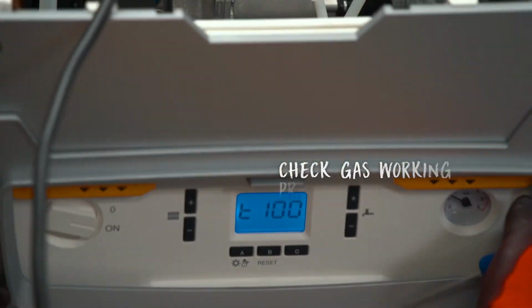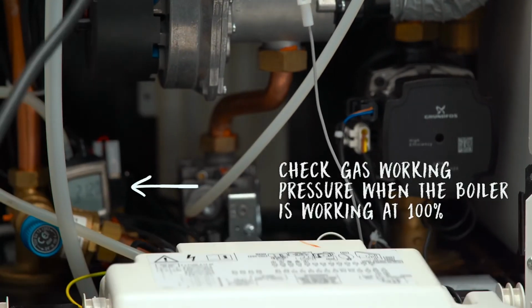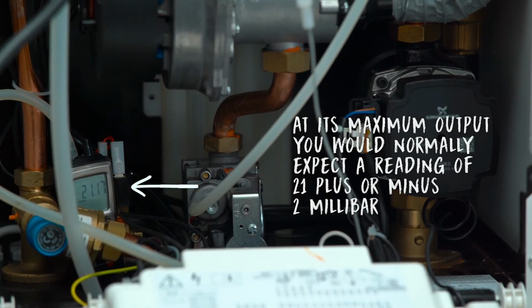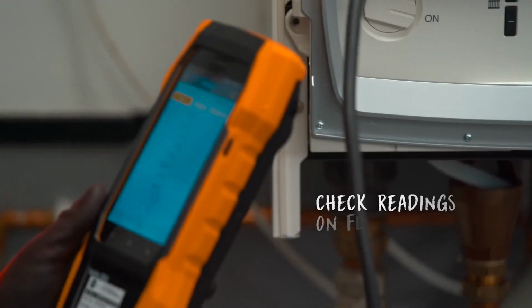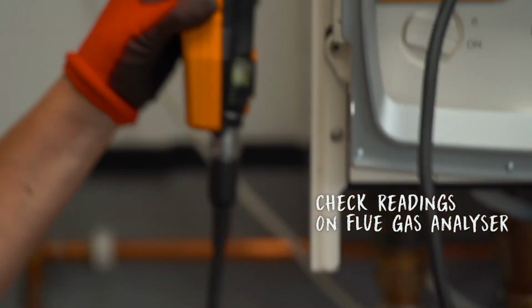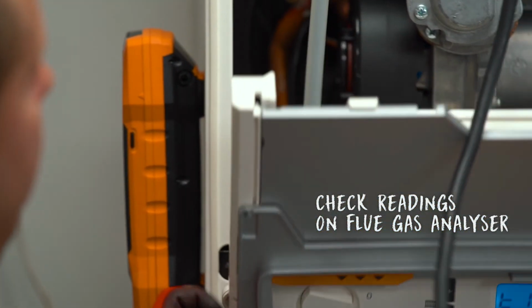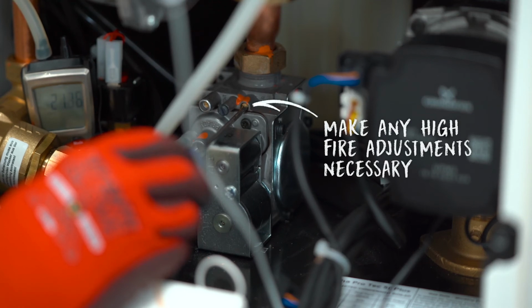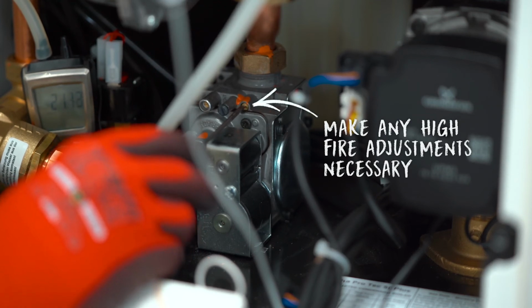Check the gas working pressure when the boiler is working at 100%. At its maximum output, you would normally expect a reading of around 21 plus or minus 2 millibar. Also check the flue gas analyzer readings when the boiler is working at 100%. You can then make any high fire or low fire adjustments necessary.